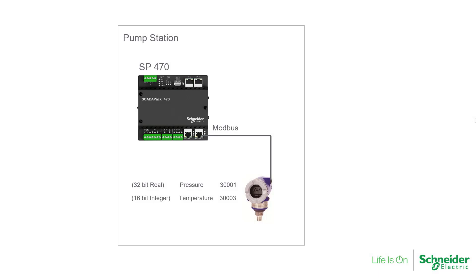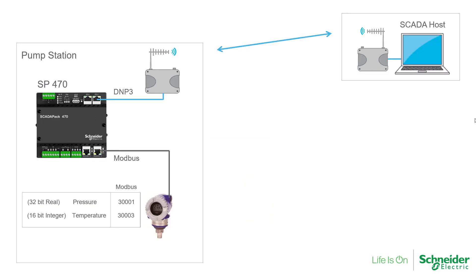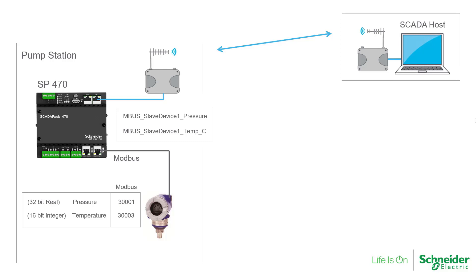Returning to our schematic of the application, we now have these two objects in the RTU that contain the data we've pulled from our pressure transmitter. Well, let's include the SCADA host now. Unlike legacy SCADA packs, the data in a 470 is saved in objects instead of Modbus registers. All this means is that you get to decide how and when you want your SCADA host to access this data. How? Well, you choose what Modbus or DNP3 address to assign to your object's data. And when? Well, if you don't want the host to access the data, then don't assign an address to the object's data.